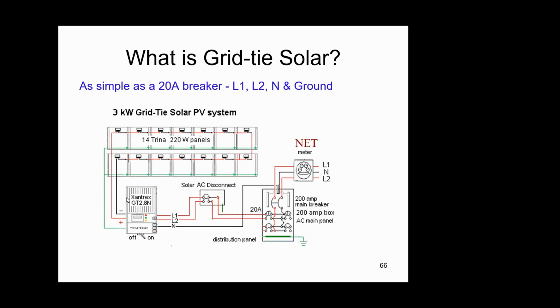That goes to the inverter. The output of the inverter is simply line 1, line 2, neutral and ground, which go to a 20 amp breaker in your distribution panel, no different from any other breaker, and that's where the backfeeding occurs. There's a requirement for an external disconnect, it's on the wall of my garage, so the power company can flip the breaker and disconnect your system if they need to.